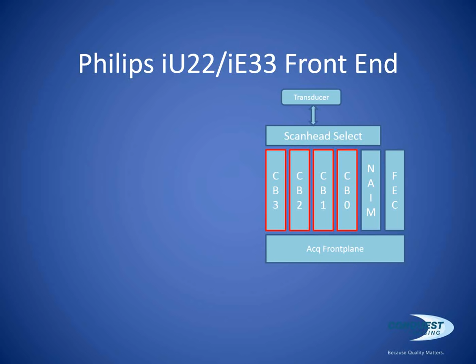You'll notice that the Acuson Sequoia has multiple TX, which are transmitter boards, and multiple BFs, which are beamformer boards. If you have an artifact within a machine, you can open up the system and rotate your transmitter boards and then rotate your beamformer boards and see if the artifact moves. If it moves when you rotate the transmitter boards, you know it's one of those TX boards, and same with the beamformer boards. So you can actually use the parts within the machine for troubleshooting. Same with the Philips iU22 and iE33. The channel boards. There are 4 channel boards within a 22 and 33. If you have an artifact that you've determined is not caused by a transducer, you can actually rotate those channel boards to determine if a channel board is causing that artifact.